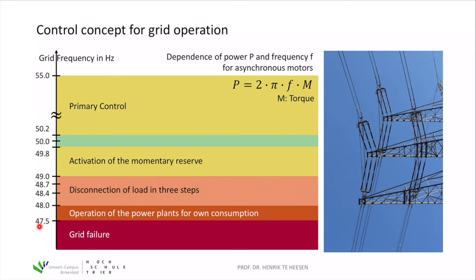If the frequency falls below 47.5 Hz, we have a full grid failure and must restart the grid from the very beginning, ramping up power plants from scratch. Normally, grid operation stays within the green band of ±0.2 Hz. In case of any deviation — mainly a frequency drop — the momentary reserve is activated and the grid is stabilized.